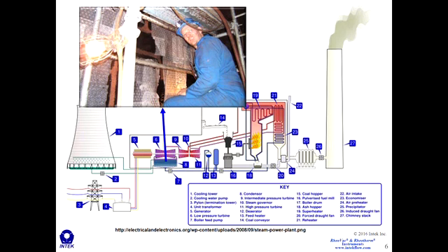This gentleman, his name is Neil. He told me once he entered a water box. He was doing an inspection before we were installing some equipment, and he showed me the pictures. There's this red-colored mud all over the walls of the water box and on the floor. He stepped into an inch-thick layer of this mud, and he told me that the mud was moving around. This is clearly one of the most foul environments in the power plant, and it may not be the most desirable place to spend your time, but it contributes to power generation efficiency in a big way.